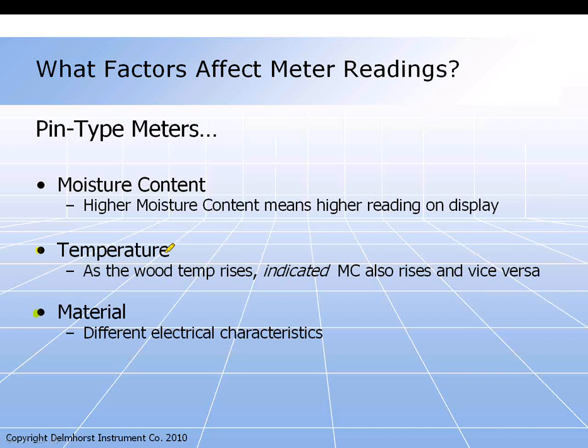Same thing with the material. Because the meters are calibrated on Douglas fir, different types of wood can give you different readings. So we give you a correction chart as well for the material that allows you to correct for the differences in the material. For those of you that are familiar with the Navigator Pro, you'll remember that it has a built-in temperature correction feature, and it has about 10 or so different materials that you can choose from. So it does these corrections automatically. And that's, again, why I'm making a big point about both of these things, because they need to be handled manually with the Tech Check and the BD2100.